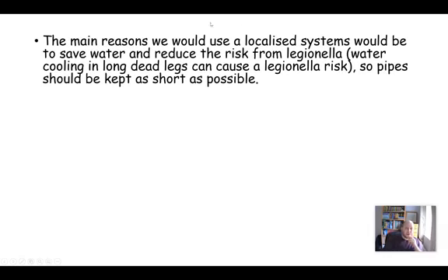So yeah, main reasons we use localized systems: it saves water, because like I say, once that water cools in the pipework, you have to run off loads of water before it starts to run warm. So we might use localized water systems to help save water and also reduce the risk from Legionella. Okay, so what we want to do is keep any pipe that doesn't have a return on it, which is technically a dead leg, as short as possible.